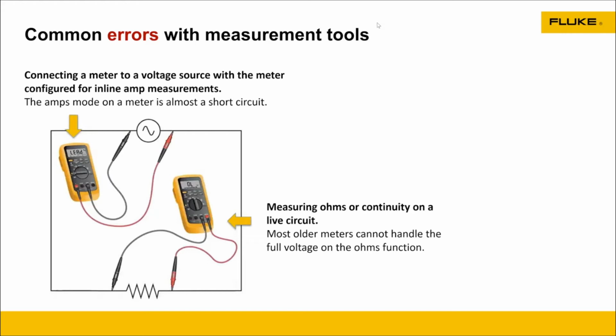So when we go into our meters, meters are designed to handle that. And Fluke's a meter company, so I am going to talk about Fluke and Fluke solutions during this presentation. And part of that is having the test leads in the right position. That would obviously cause some type of arc fault or something to happen of that nature. So if you have the test leads in, maybe in the current position, you think you're in the voltage one, we'd want to have a lead indicator or something on that.